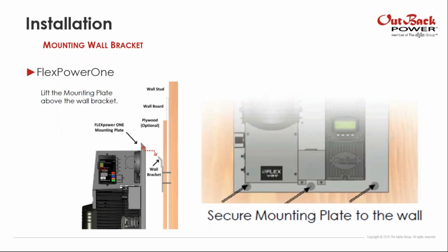Once you have installed the mounting wall bracket, it is easy to just lift the mounting plate above the wall bracket. You just slide the mounting plate, and then you secure the mounting plate to the wall with the screws that need to be put in the lower part. Those three, and that's it. You don't need to present the inverter first and then use different kinds of screws or anything. You just lift the mounting plate and secure it, and that's it. It's very easy.